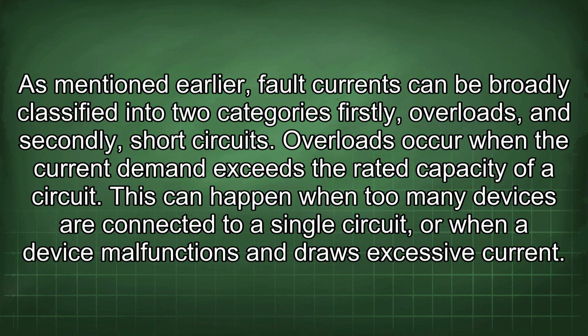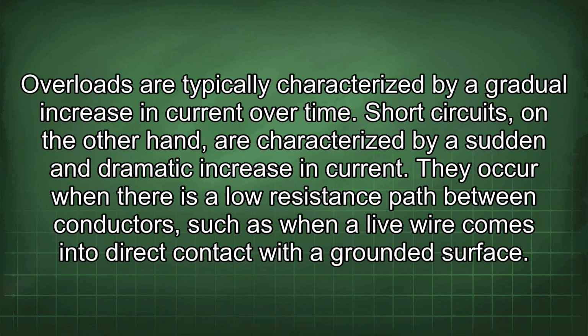As mentioned earlier, fault currents can be broadly classified into two categories: firstly, overloads, and secondly, short circuits. Overloads occur when the current demand exceeds the rated capacity of a circuit. This can happen when too many devices are connected to a single circuit, or when a device malfunctions and draws excessive current. Overloads are typically characterized by a gradual increase in current over time.